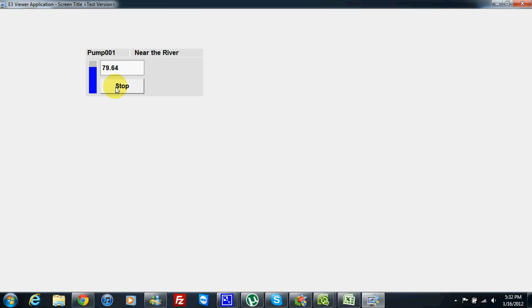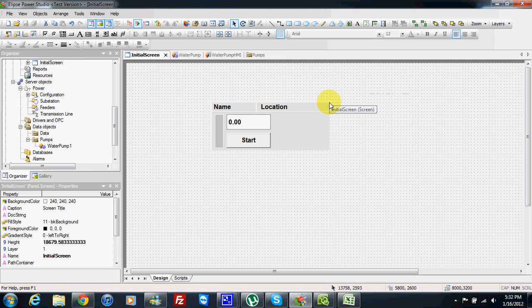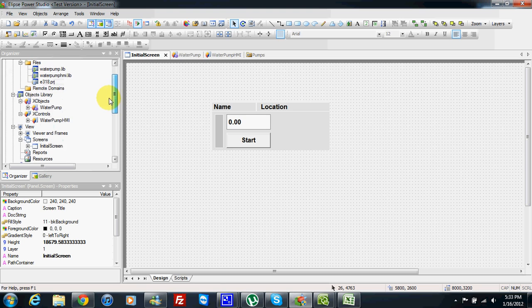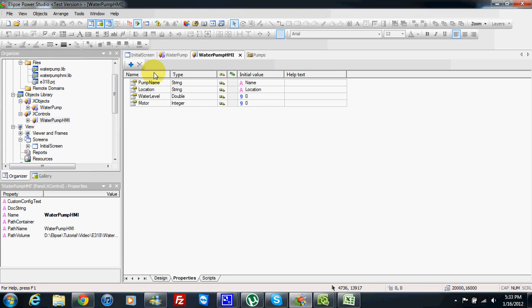But the problem is when I have 10 water pumps in my screen I have to do this linking 10 times. If I have four links for one, I need to make 40 links. So this is not so convenient. If I look very carefully I will find out that the properties of my XObject are the same as the properties of my XControl — they are absolutely the same. So why link 1-to-1, 1-to-1, 1-to-1 when I can directly give to the HMI the reference of my water pump instance?